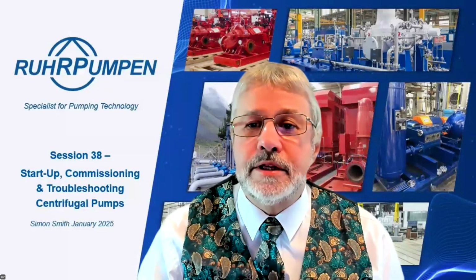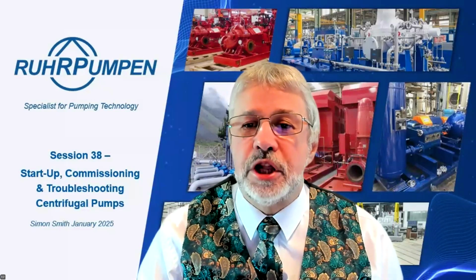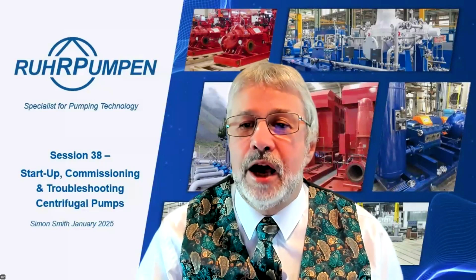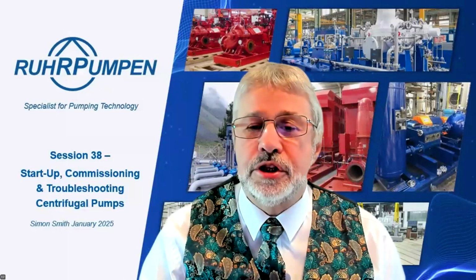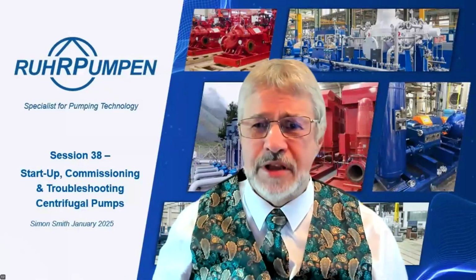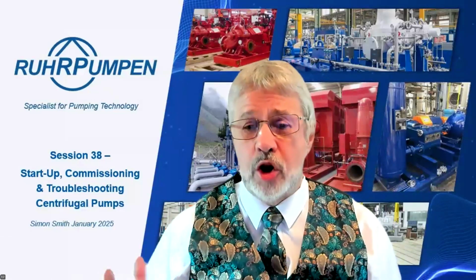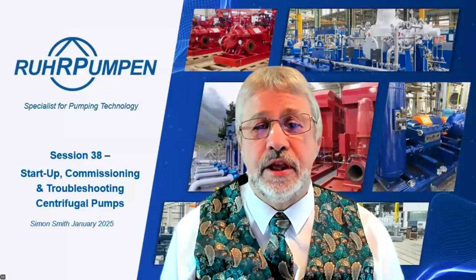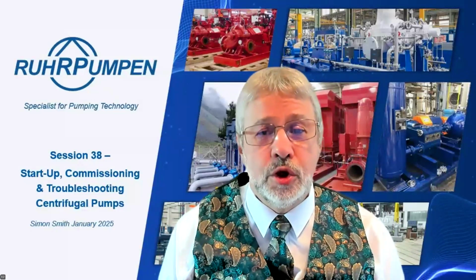Amir Hasnain says, please explain a little about the use of an eccentric reducer, top side up or top side down. Which configuration shall be used and where? Secondly, how far shall it be installed from the pump suction nozzle? An eccentric reducer would be installed directly on the suction of the pump. It doesn't need to be several pipe diameters down line. It's quite common for it to be right up against the suction of the pump, and it's usual to install it with the flat side on top.